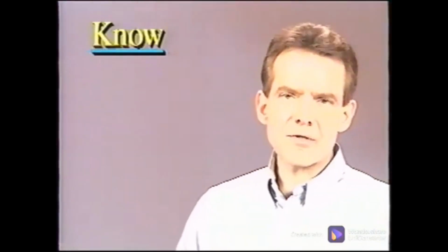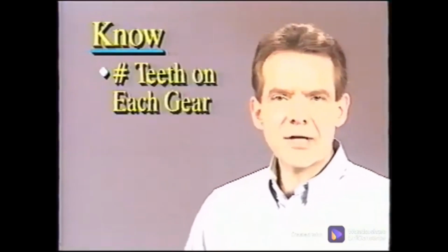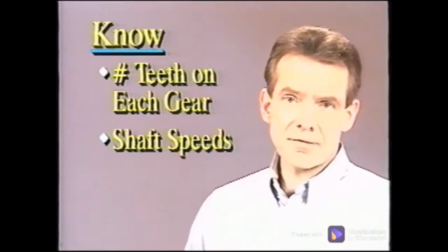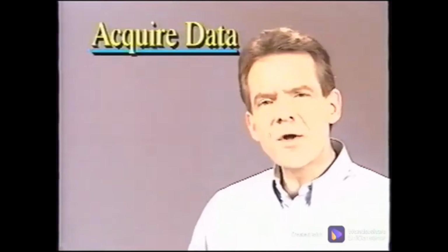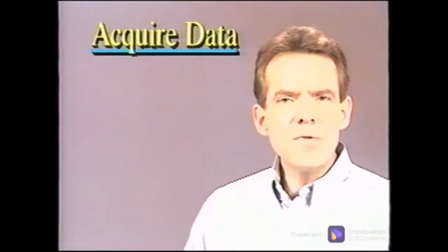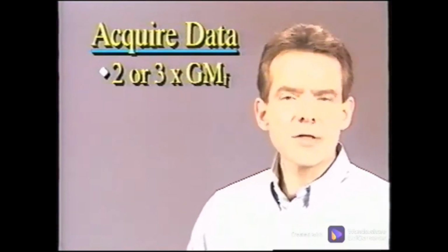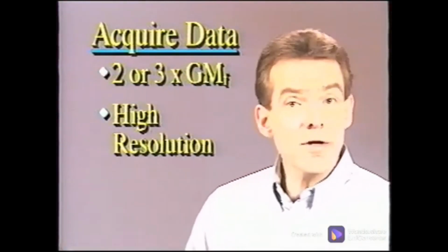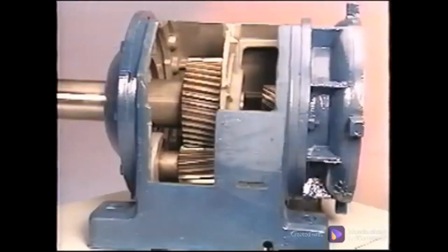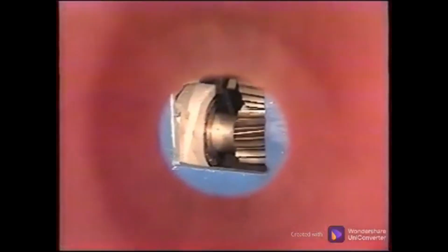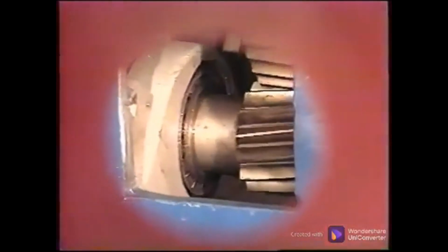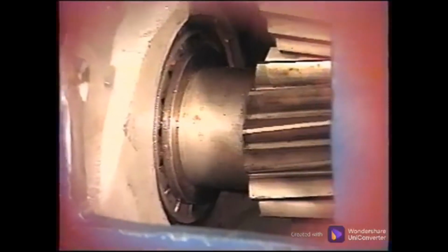For accurate diagnosis, you need to know the number of teeth on each gear, the speed of each shaft, and the gear type. When collecting data on gear drives, be sure to acquire data to include 2 or 3 orders of gear mesh and use adequate resolution to separate sideband peaks. On multiple reduction gearboxes, use tunnel vision to zero in on the desired frequencies so you can better diagnose problems.